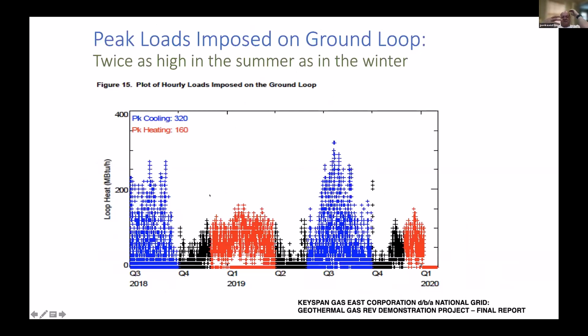As another example, just to visualize that a little bit differently. The red is the heating, the wintertime, and the blue is the summertime. This is the cooling energy. And you can see the peak cooling is about twice as high as the peak heating in terms of loop field energy. On the peak day, we're extracting only about half the energy from the loop field that we're putting into it for cooling. In other words, the cooling is much, much higher than what we're pulling out of the loop field in the wintertime on a single day.